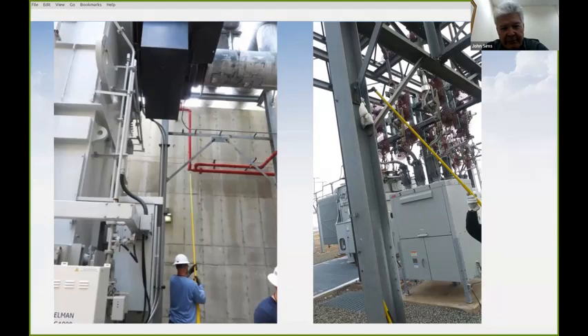That's been fantastic. Another example on the right, and this is a pretty good example. I can't show the detail because it's already been cleared up, but you see the typical bushing guard around the phase connectors in the substation. Because of the proximity and size of those guards, they created an overlap, so one circle, if you will, would overlap the adjacent phase.